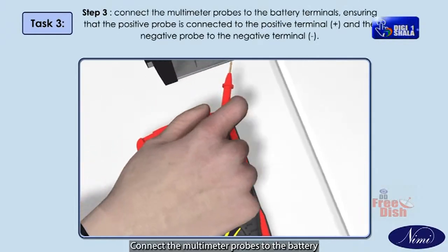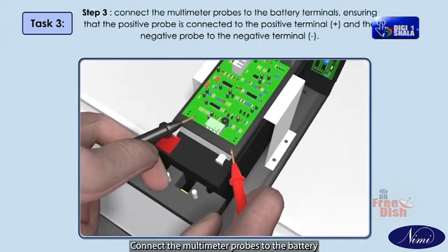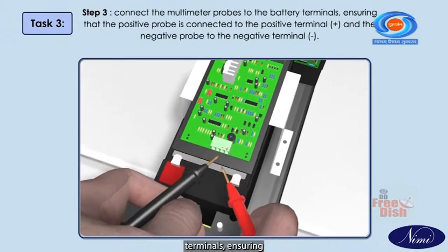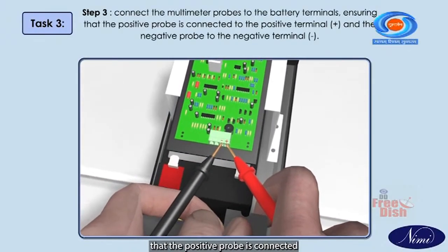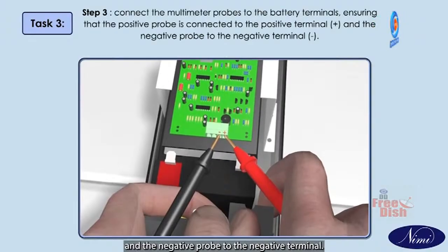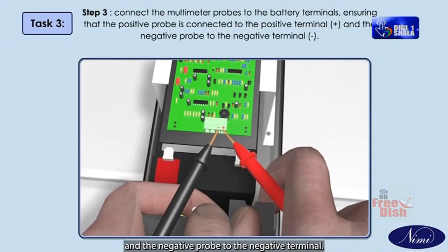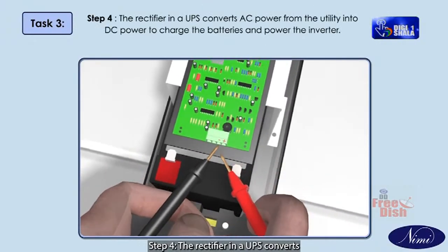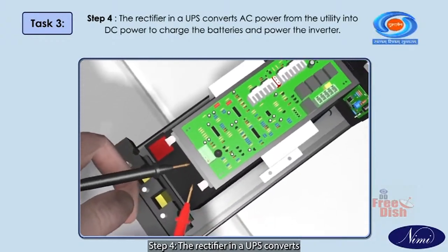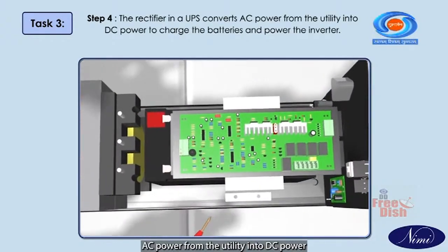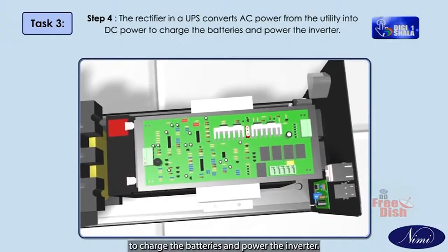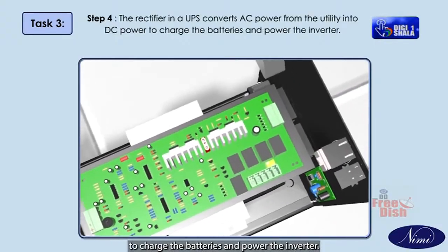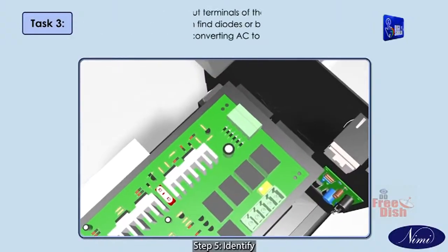Step 3. Connect the multimeter probes to the battery terminals, ensuring that the positive probe is connected to the positive terminal and the negative probe to the negative terminal. Step 4. The rectifier in a UPS converts AC power from the utility into DC power to charge the batteries and power the inverter.